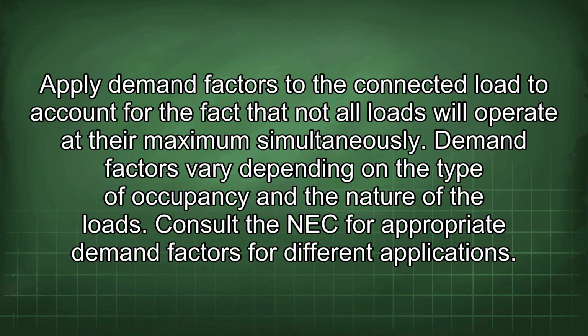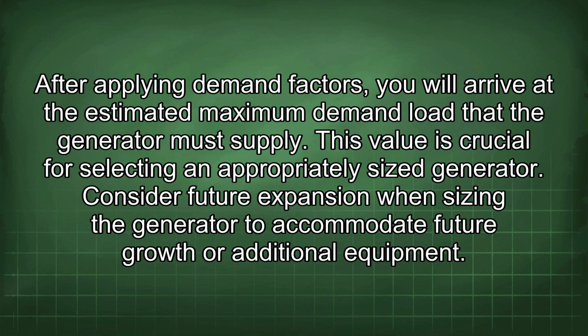Apply demand factors to the connected load to account for the fact that not all loads will operate at their maximum simultaneously. Demand factors vary depending on the type of occupancy and the nature of the loads. Consult the NEC for appropriate demand factors for different applications. After applying demand factors, you will arrive at the estimated maximum demand load that the generator must supply. This value is crucial for selecting an appropriately sized generator.